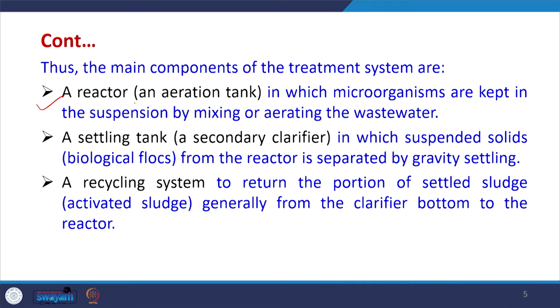The main components of the activated sludge treatment system are: a reactor, which is an aeration tank in which microorganisms are kept in suspension by mixing or aerating the wastewater; a settling tank, which is a secondary clarifier where suspended biological flocs from the reactor are separated via gravitational settling; and a recycling system to return a portion of the settled sludge from the clarifier bottom to the reactor to maintain the required amount of activated sludge.